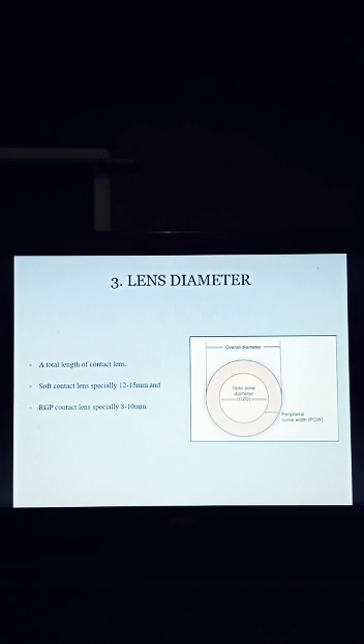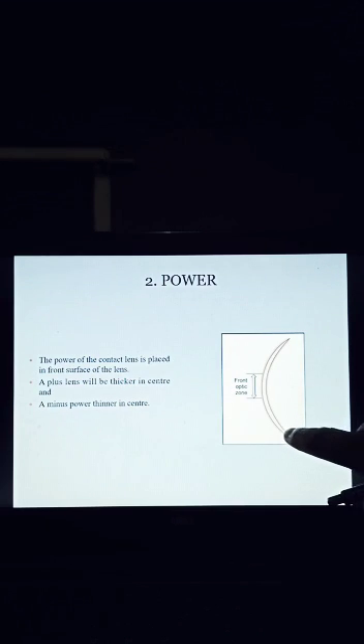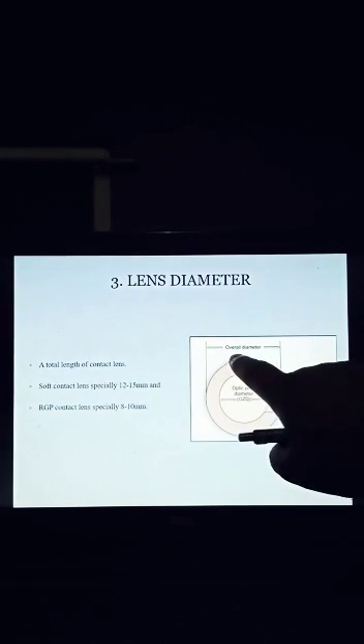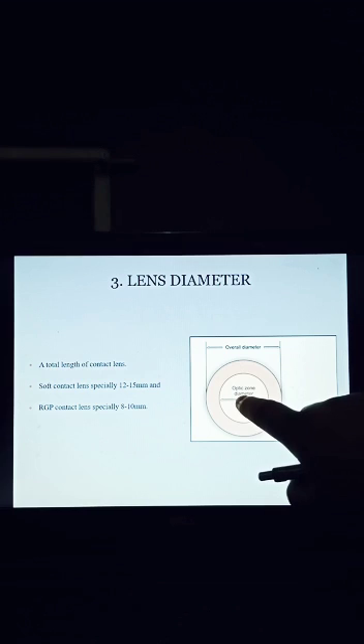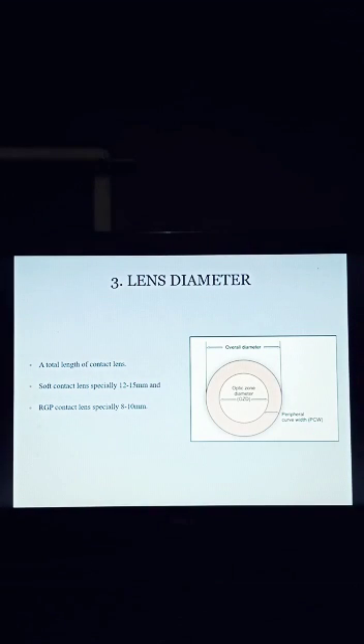Number 3: Lens diameter. Lens diameter means the total length of the contact lens. See the diagram — lens diameter means from here to here; this is the overall diameter, or total diameter. Overall diameter and total diameter are the same. The center of the contact lens is the optic zone. Soft contact lens and RGP contact lens diameter is different — soft contact lens diameter is 12 to 15 millimeters, and RGP contact lens diameter is 8 to 10 millimeters. The full form of RGP contact lens is Rigid Gas Permeable.